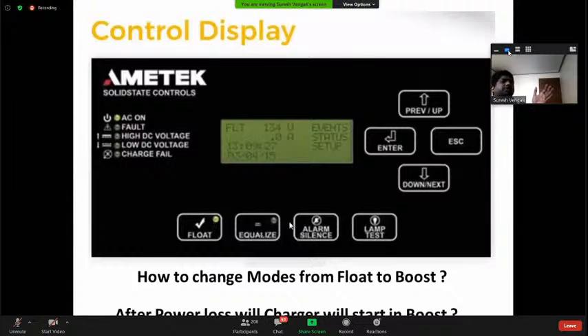Here I mentioned boost - you should read boost and equalize as the same thing. Float to equalize or equalize to float is up to you. After power loss, if it is in auto mode, it will go into equalization mode; if it is not in auto mode, the battery charger always stays in float mode only.